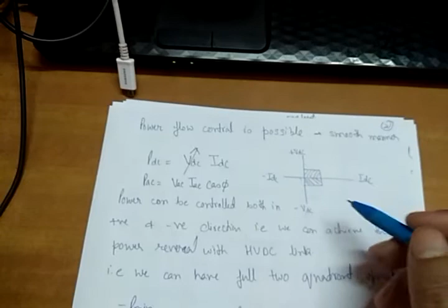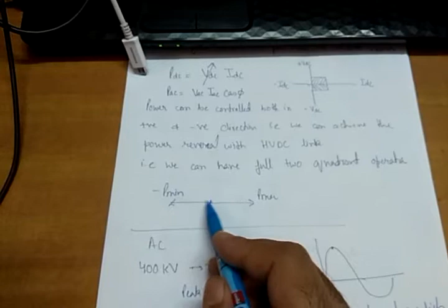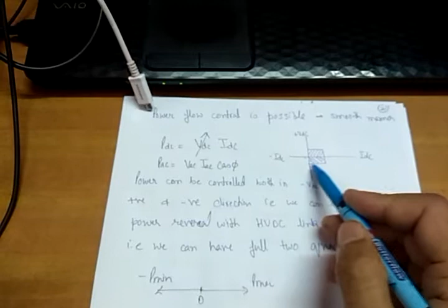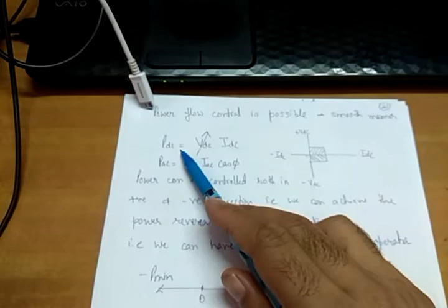This way we can achieve power reversal with an HVDC link by simply controlling the voltage. We can control the power not only up to its maximum value, but we can also control it up to its minimum value, which is negative. This is called power reversal, because if we take a voltage in the negative quadrant, it will give us a negative current here. That means the power flow has been reversed.